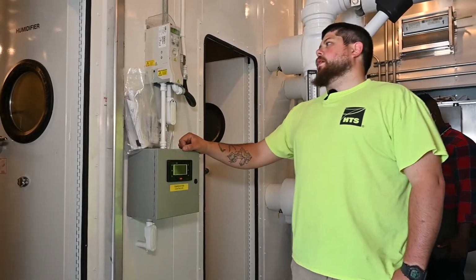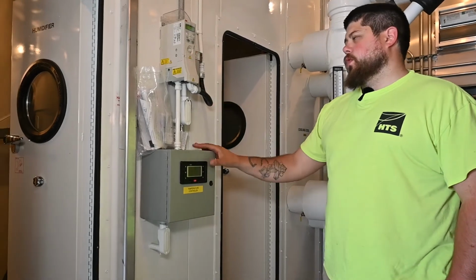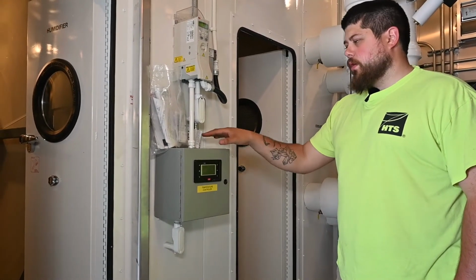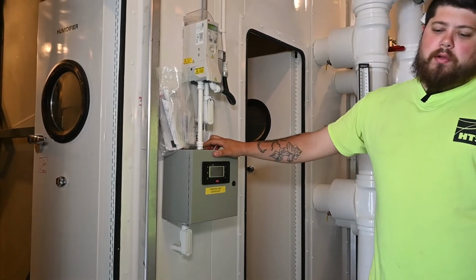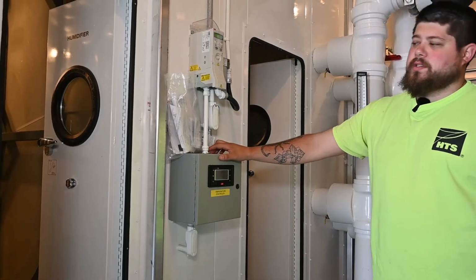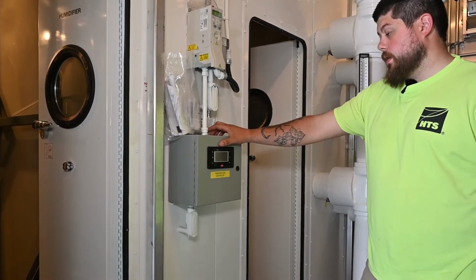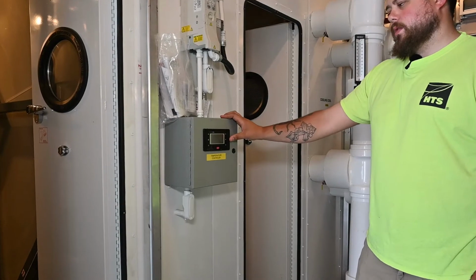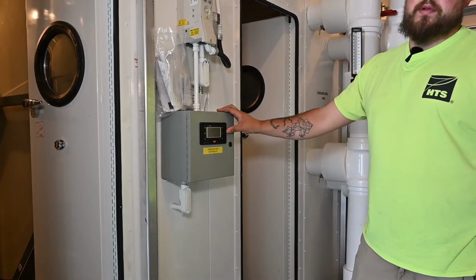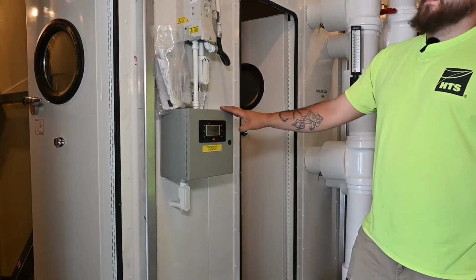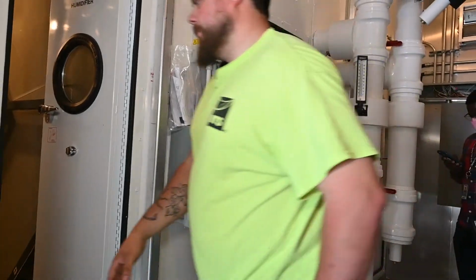Right here we have our heat wheel VFD and the controller that's tied in with the wheel. This controller here is basically used to control the wheel based off of temperature. It allows it to have its own internal defrost method. This is also tied in through BACnet with Zenergy for them to take a look at it and be able to control it and manipulate it as they see fit. We can take a step into this section.